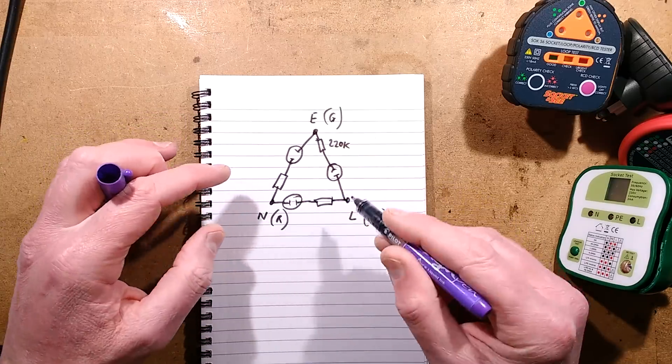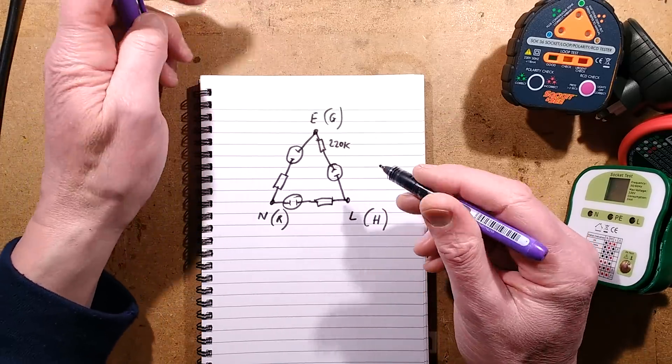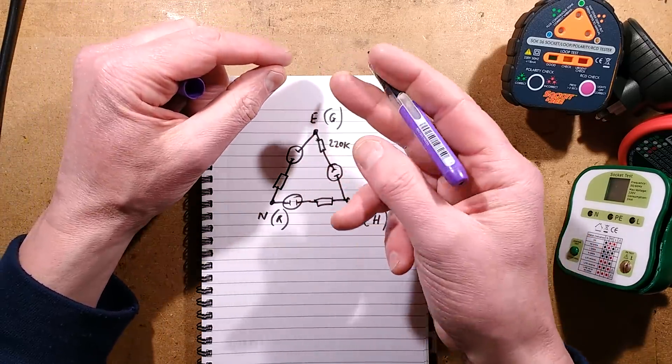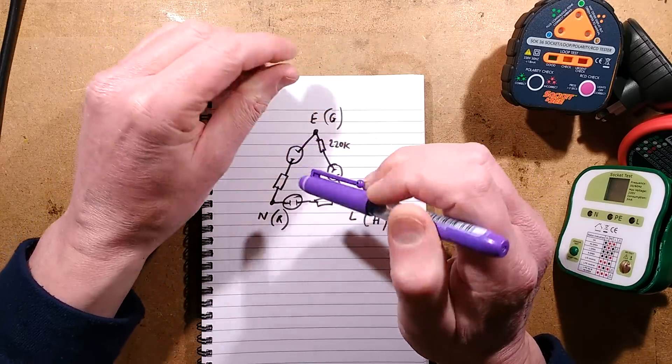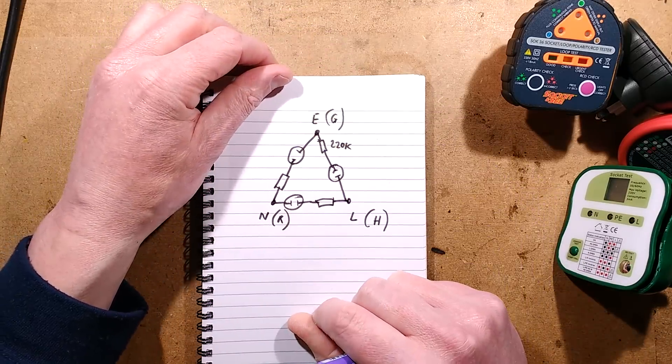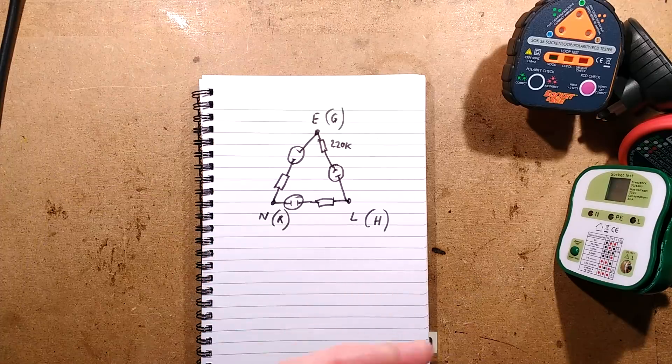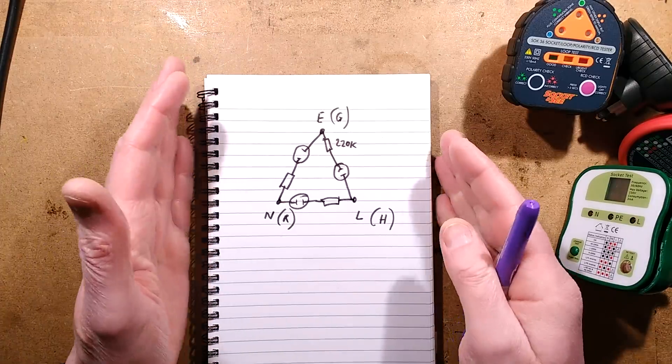Now these things can't detect a swap between neutral and earth because technically speaking they're bonded together in most installations. They're not in this installation because this is a TT electrical system that's feeding this particular building.